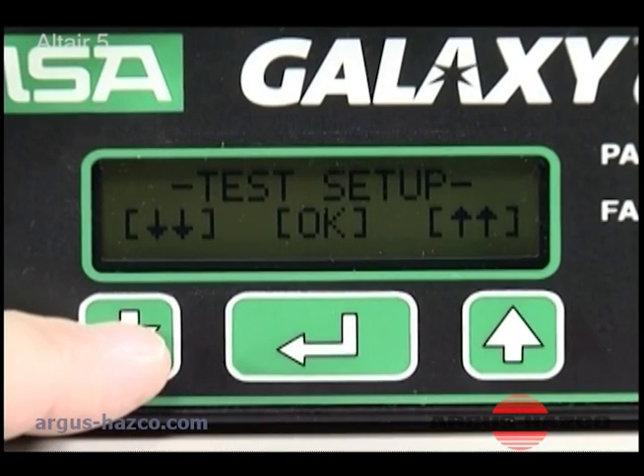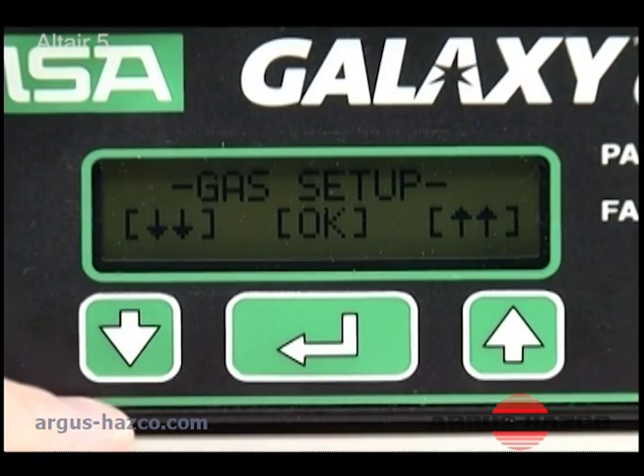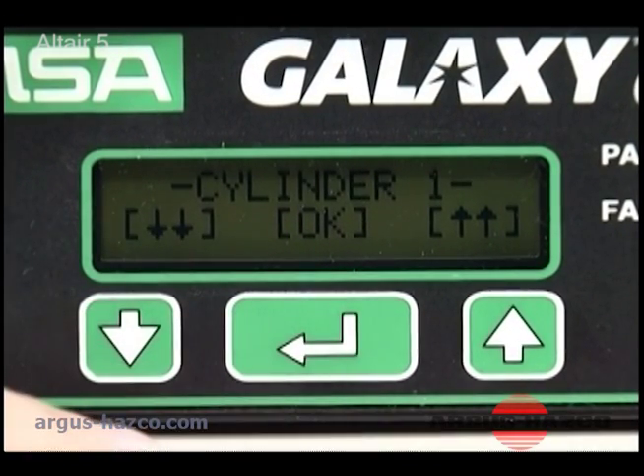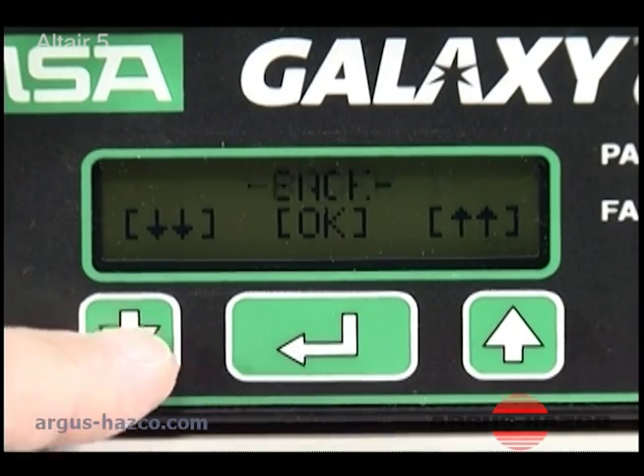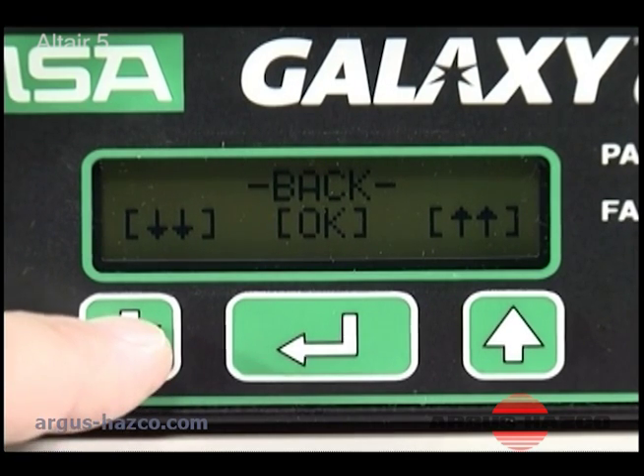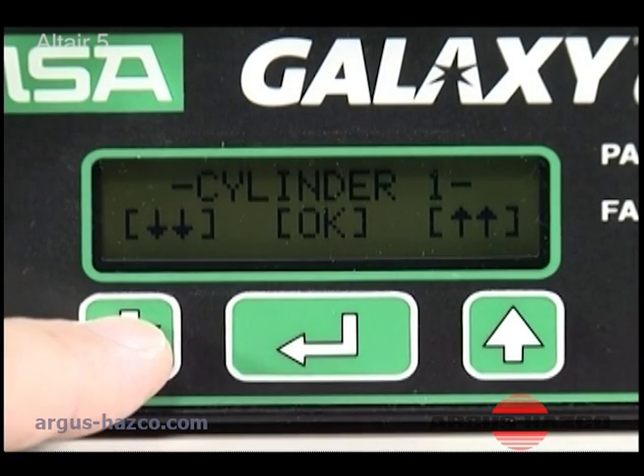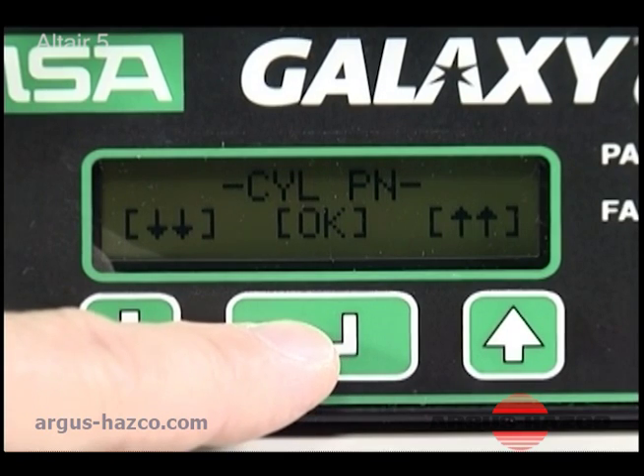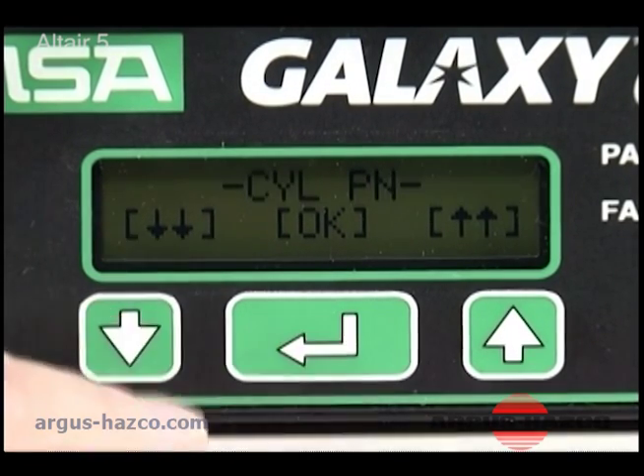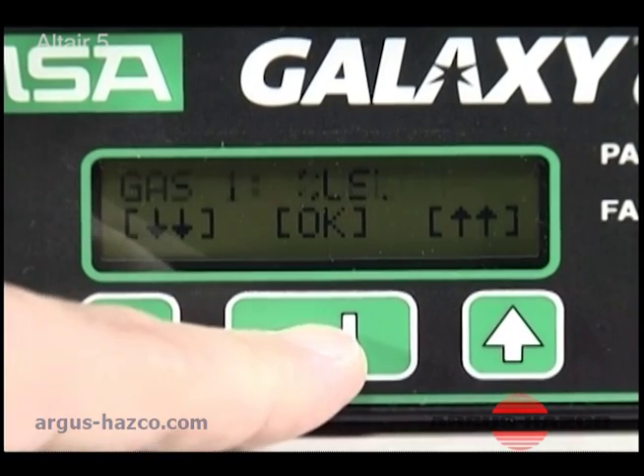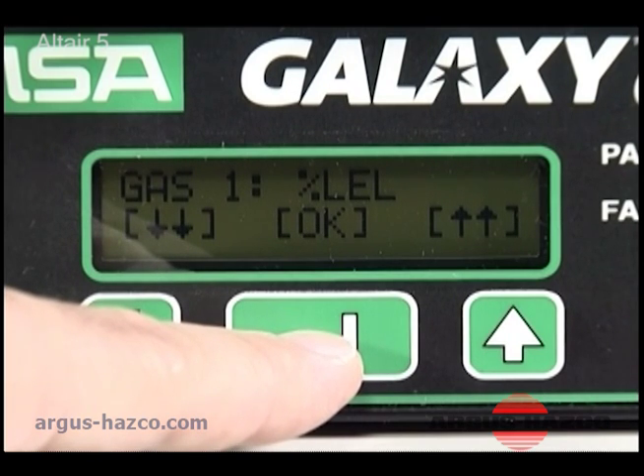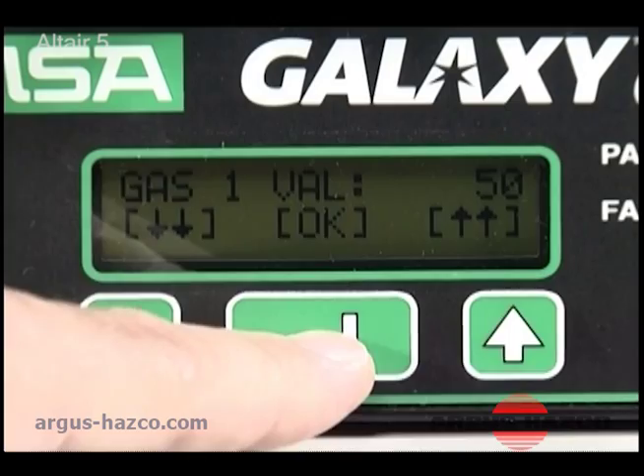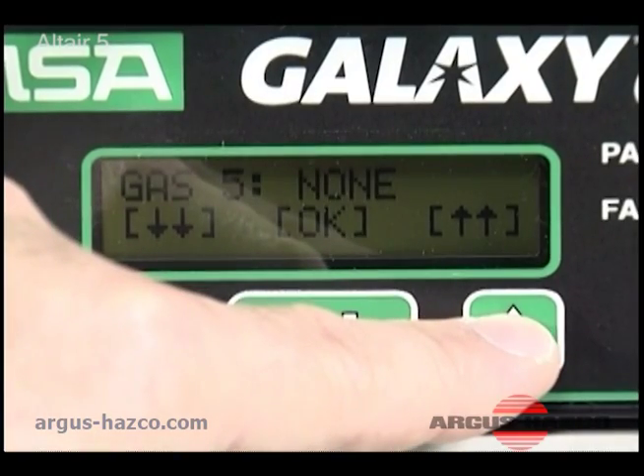Go to Gas Setup to change cylinder gas assignments. The Galaxy system can accommodate up to 3 cylinder holders. Users can select cylinder gas assignments by cylinder part number or by gas and value. To select by gas and value, go to Cylinder Custom and scroll through the list. Select up to 5 gases for each cylinder. If you have fewer than 5 gases, set the remaining gases to None.